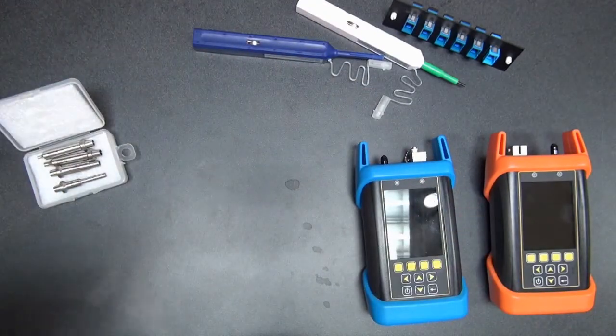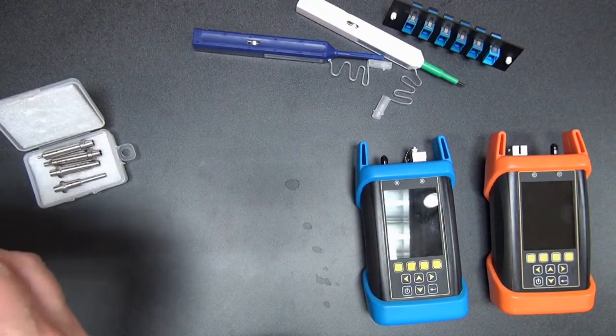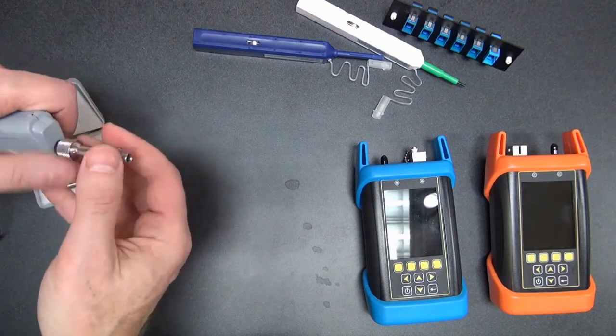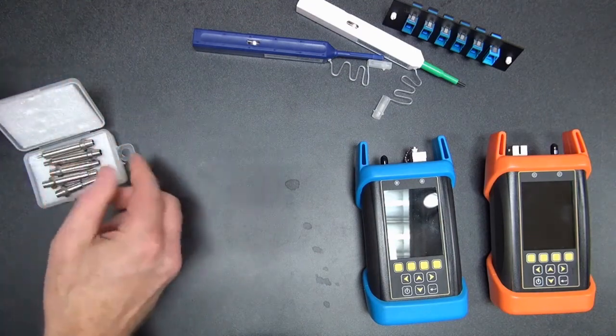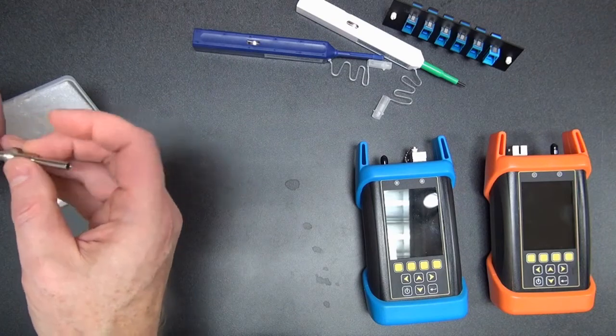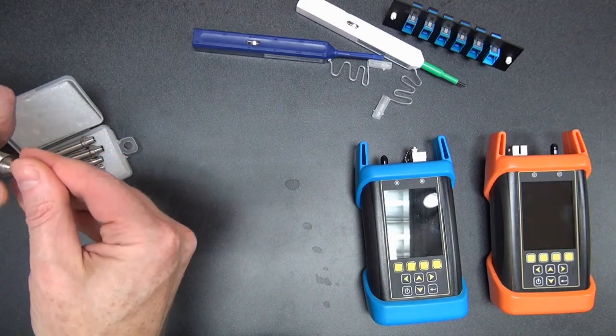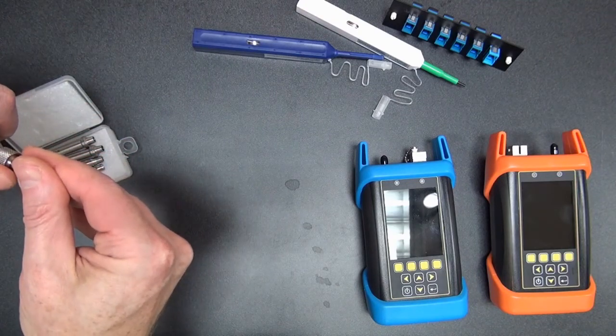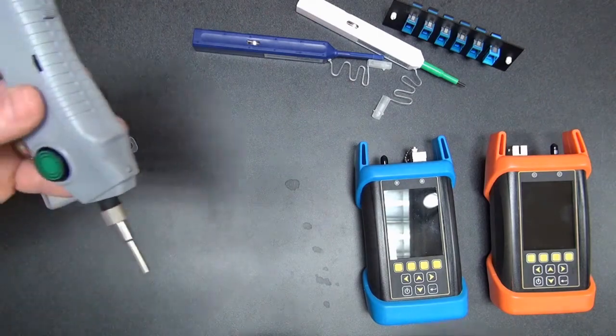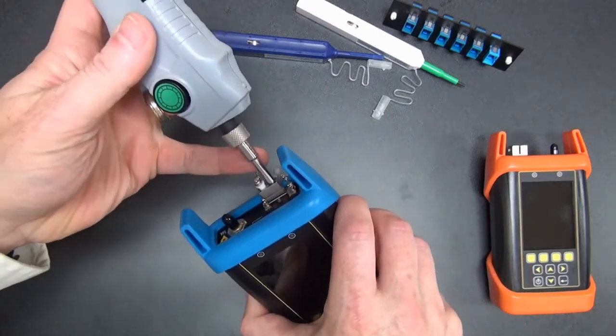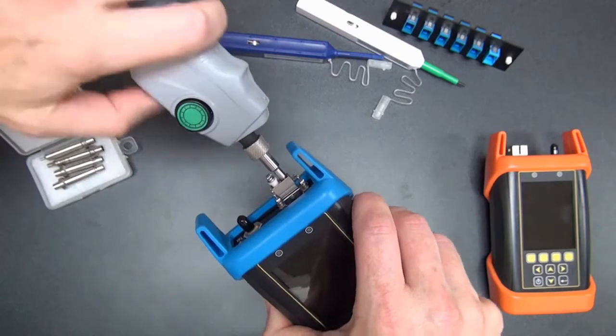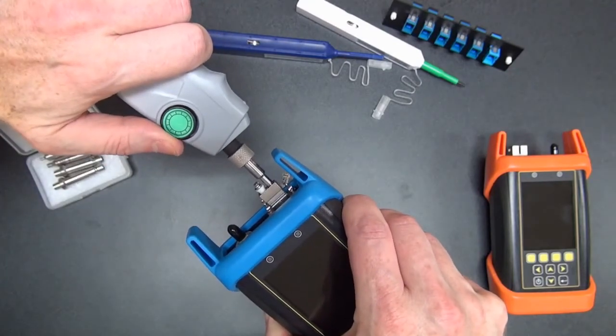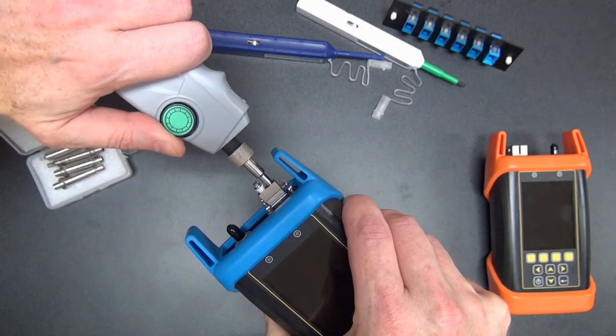So most of these probe microscopes come with removable tips. We simply remove the SC tip and we put the LC tip on. Once we have that attached, now we can plug into our LC port, again we wait for the end face image, and then we can simply use the focus wheel and focus the image.